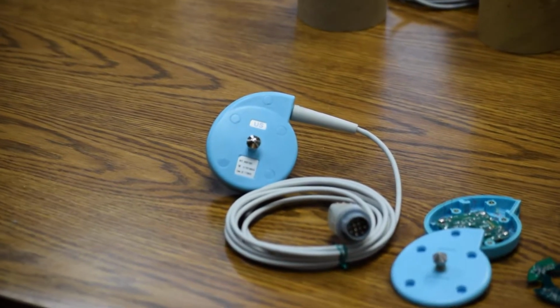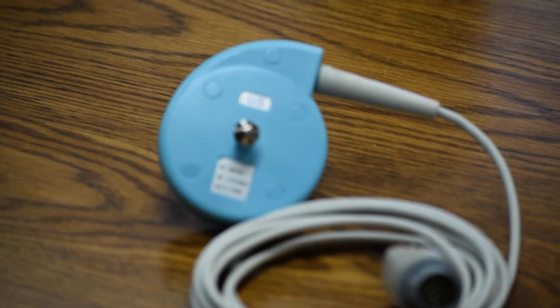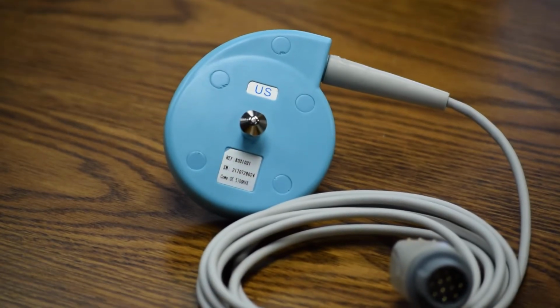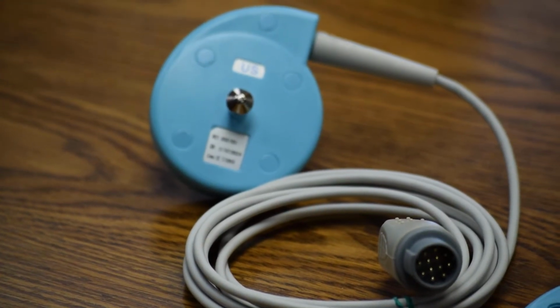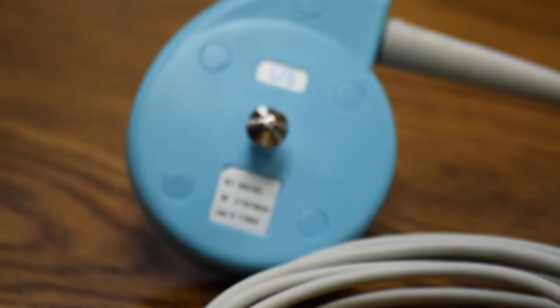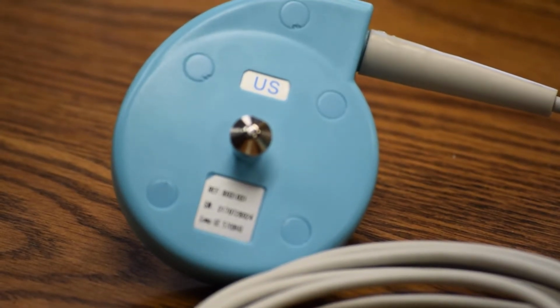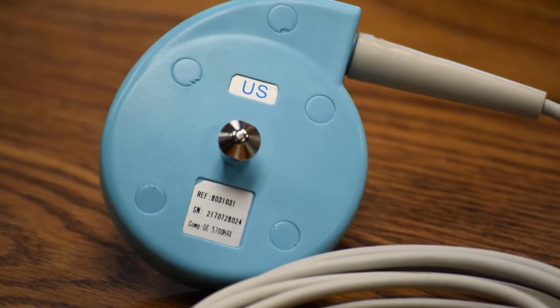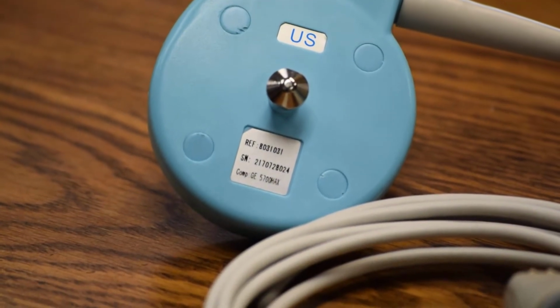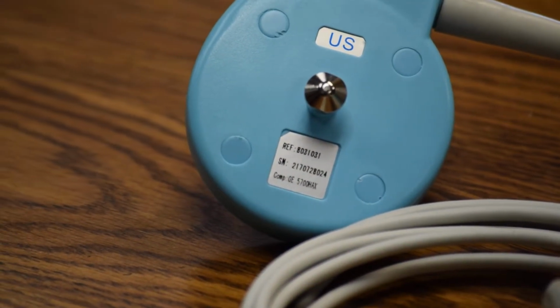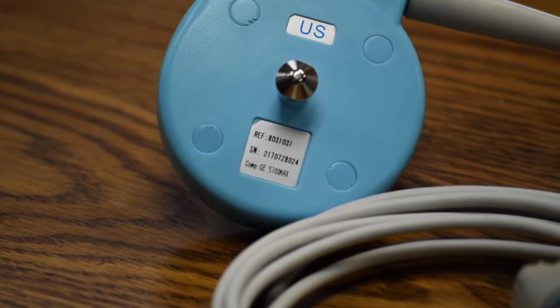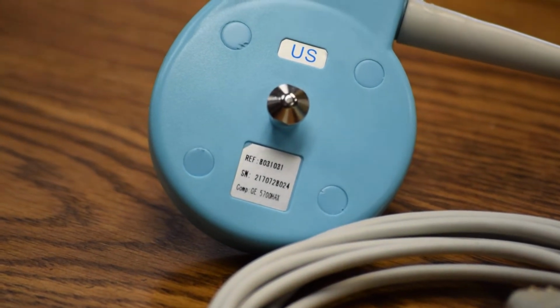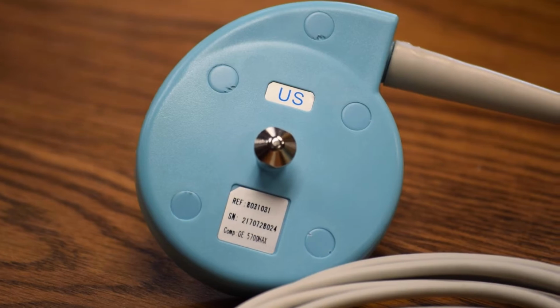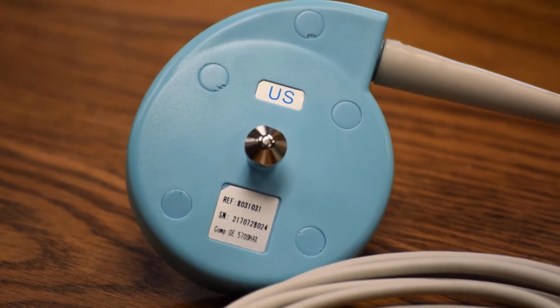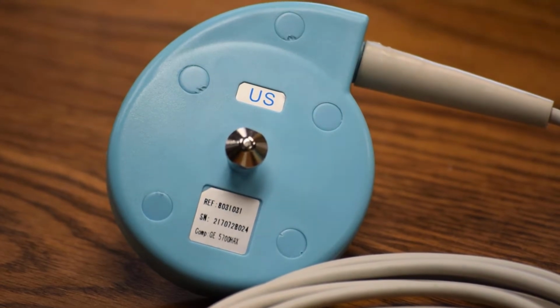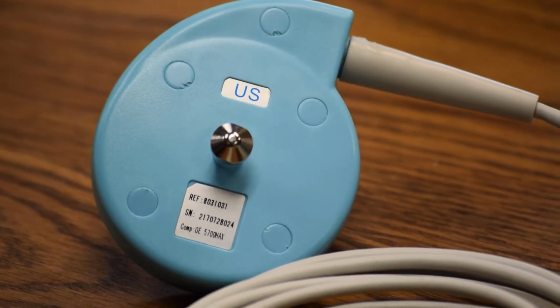This particular ultrasound transducer is for GE Corometrics fetal monitors 120, 170 and 250 series models. It is not the original manufactured by GE Corometrics but a generic non-OEM with labels stating reference number as 8031031, serial number 2170 72 80 24. There is a marking saying COMP, which stands for compatible, and marked as GE5700HAX. That means compatible to GE model 5700HAX.